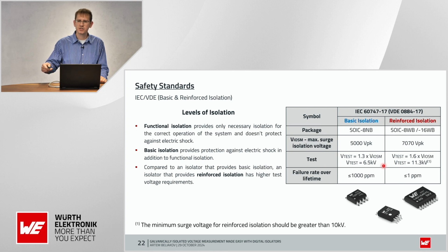But if you check the test voltage for basic isolation, you can see that the test voltage is 1.3 times the maximum surge isolation voltage, and for reinforced isolation, the test voltage is 1.6 times the maximum surge isolation voltage.